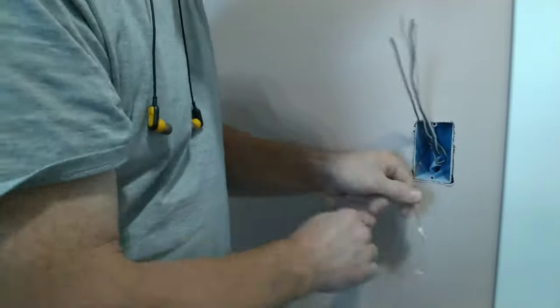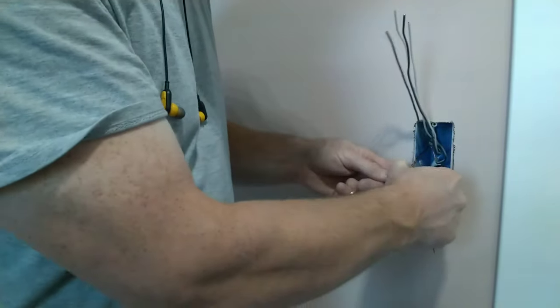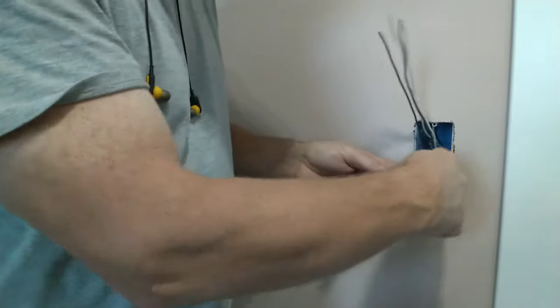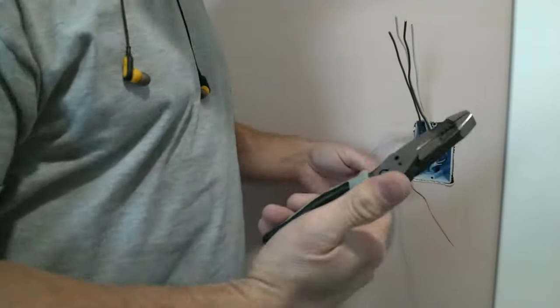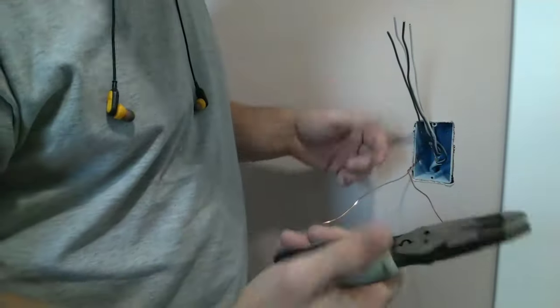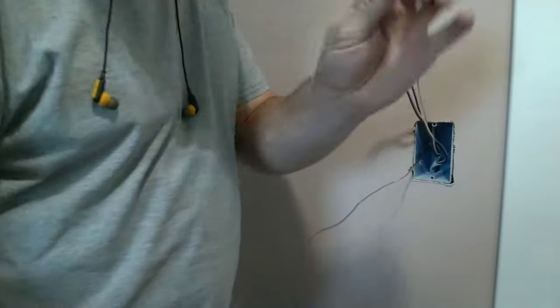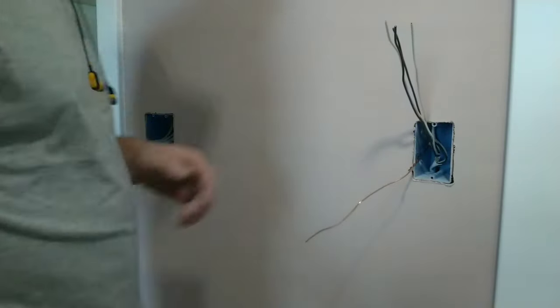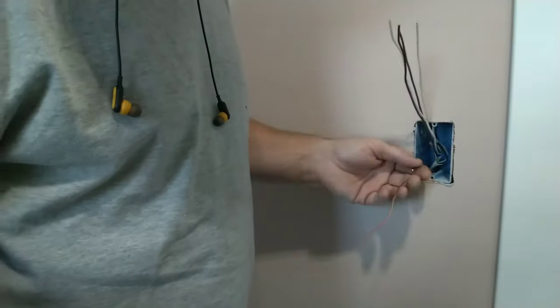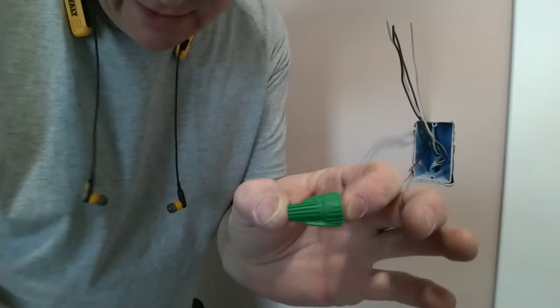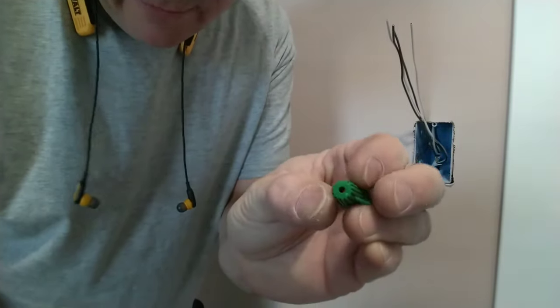Take these grounds and twist them together until you get approximately 5 inches from the back of the box to the front. Take your Klein cutters or dykes, cut off the extra copper wire, throw it in your scrap bucket. Now on this installation, I use greenies. These are grounded wire nuts, and they're especially made for doing pigtails off of ground.